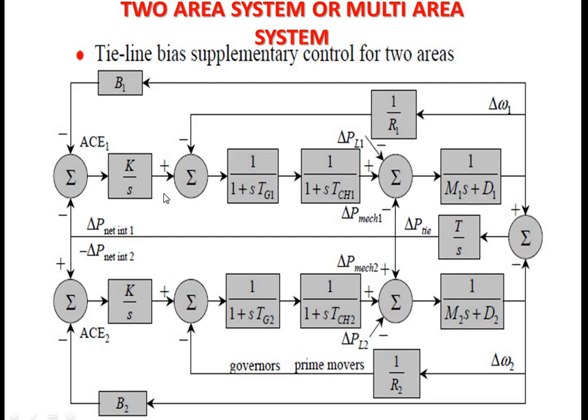That positive change in frequency will give a decrease command to the power generation. So in order to give a positive change in frequency, we are purposely maintaining a negative sign in this integrator. Likewise we can include the area control error block to the entire load frequency control.